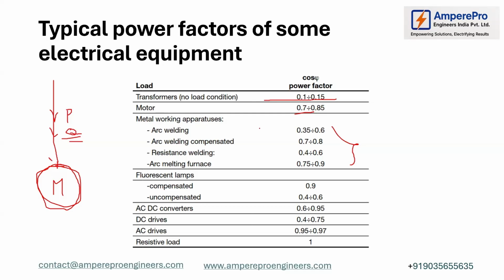So when you keep these loads in any factory, obviously your power factor comes down, okay. So to compensate that, because when the power factor is very low, obviously we are drawing more apparent power from the grid, so that all the equipments are being oversized. Because of this reason only, your utility is putting the penalty onto it, right?